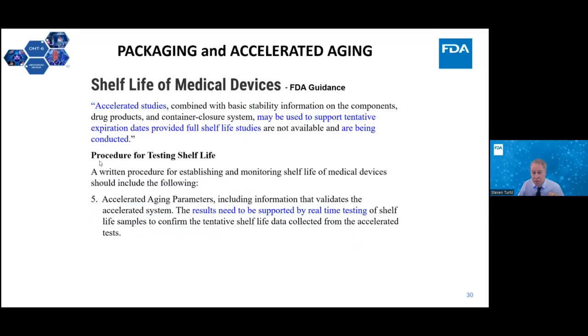And this is from our FDA guidance document. That's what I provided the link for. Test procedure for testing shelf life. The relevant items are number 5 and 6. Written procedure for establishing and monitoring shelf life of medical devices should include the following: accelerated aging parameters. So that's basically the conditions, the temperature and time.